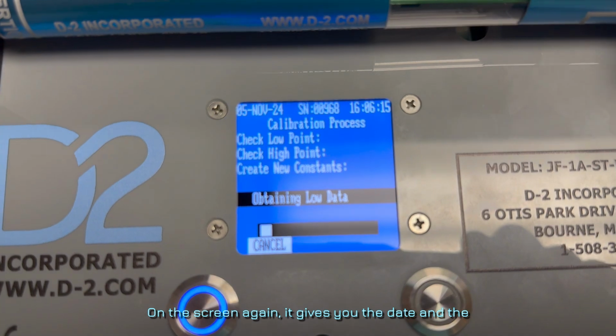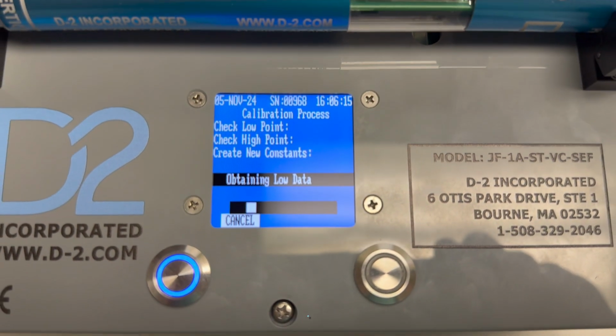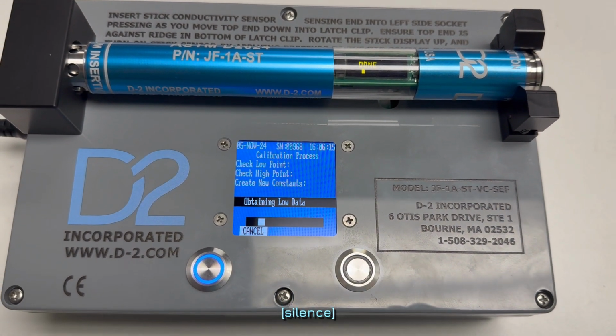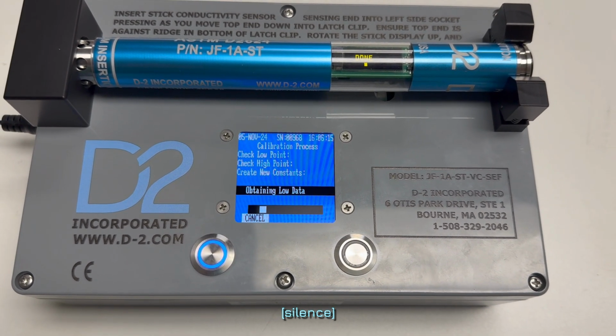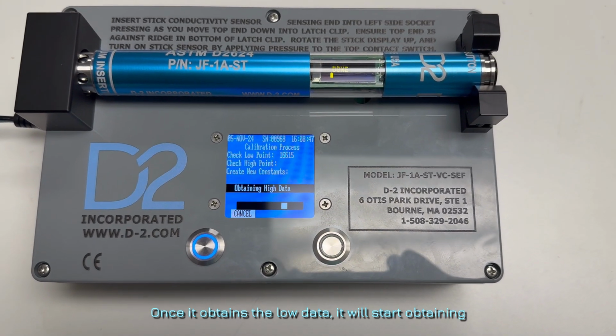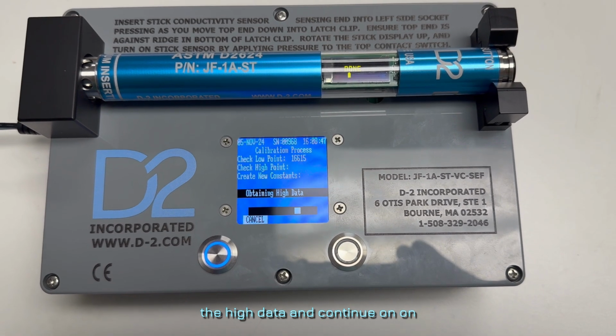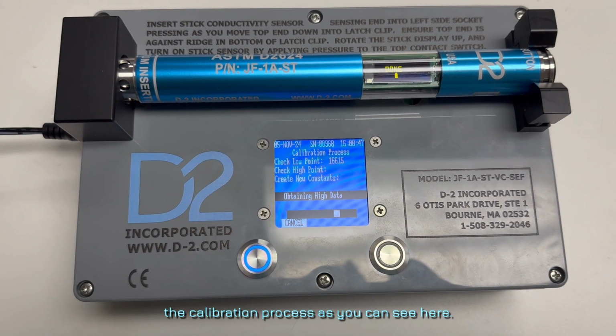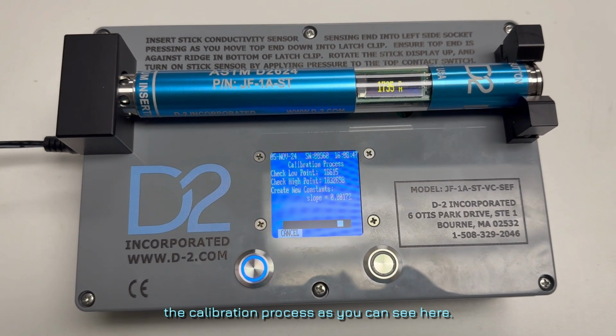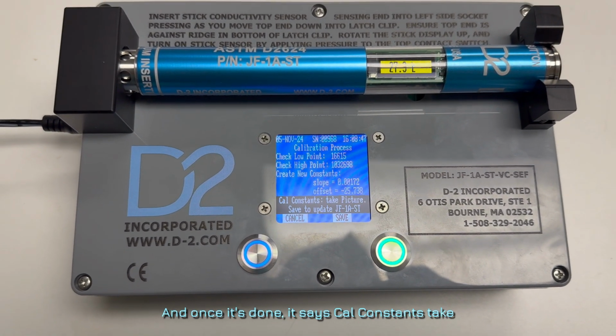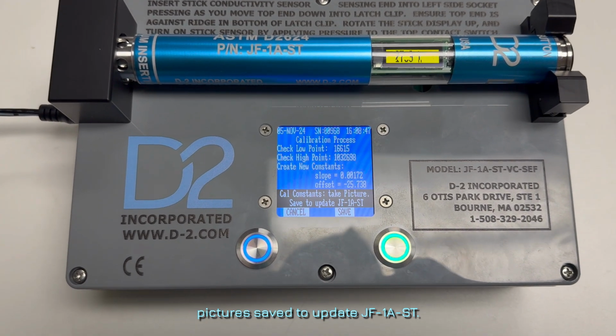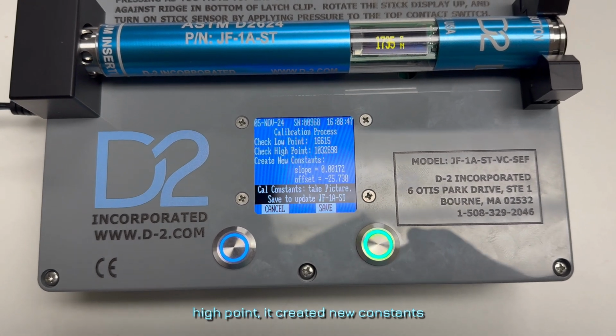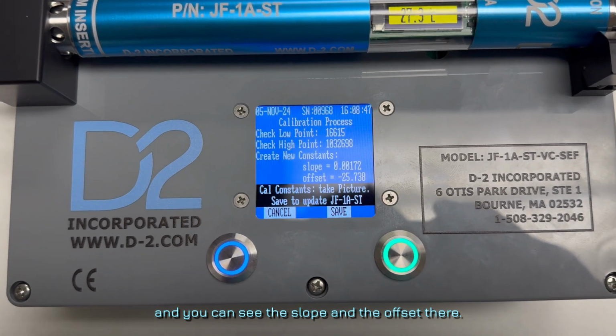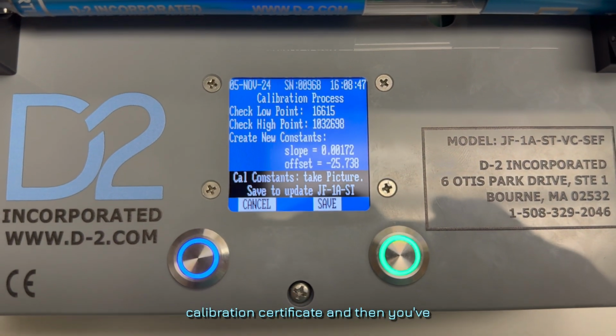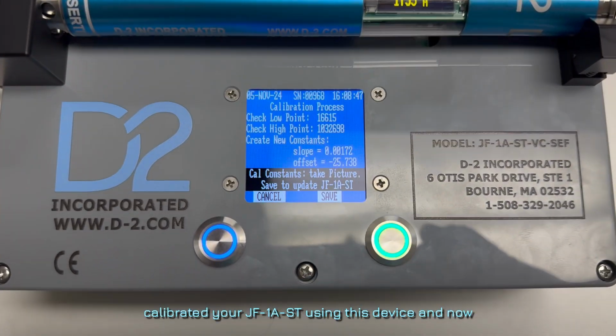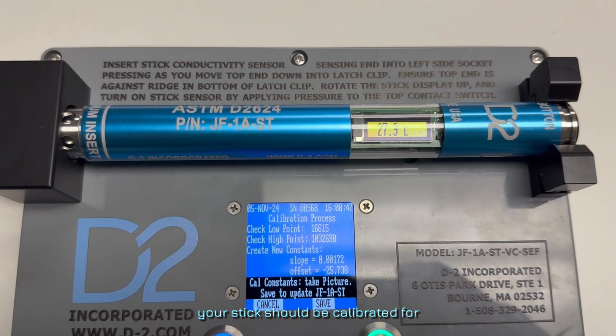On the screen again, it gives you the date and the time that you are running the calibration. Once it obtains the low data, it will start obtaining the high data and continue on the calibration process, as you can see here. And once it's done, it says Cal Constants take picture, save to update JF1A ST. You can see here, it checked the low point, it checked the high point, it created new constants, and you can see the slope and the offset there. And if you take a picture of this, it counts as a calibration certificate, and then you've calibrated your JF1A ST using this device, and now your stick should be calibrated for the next year.